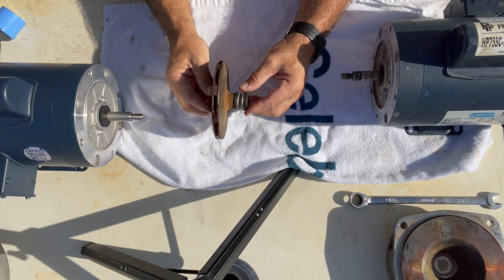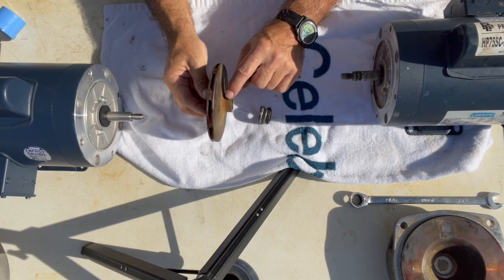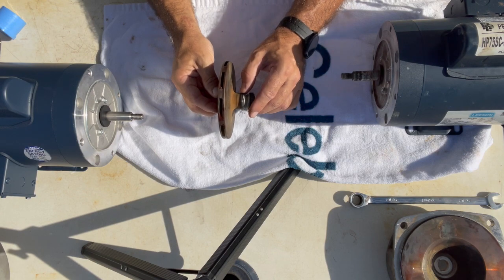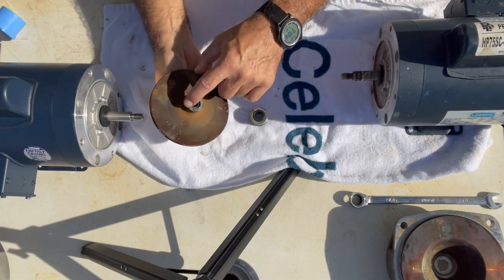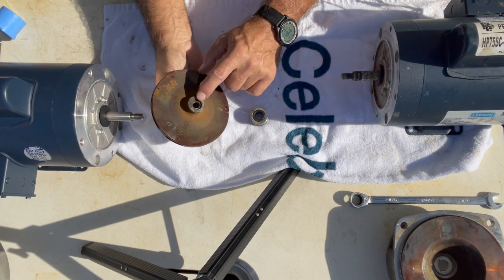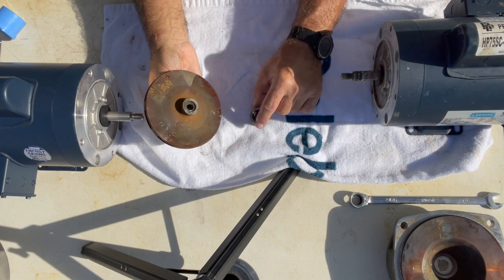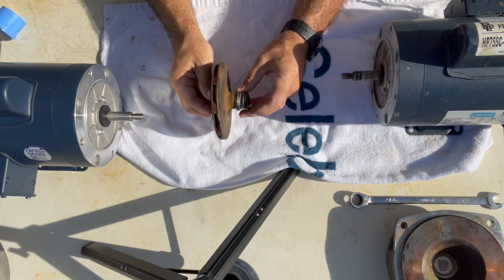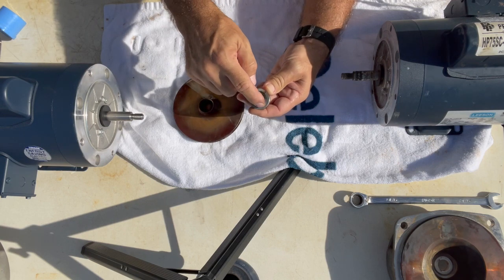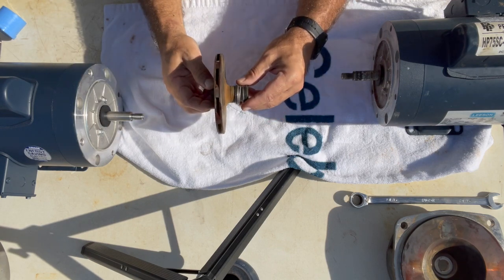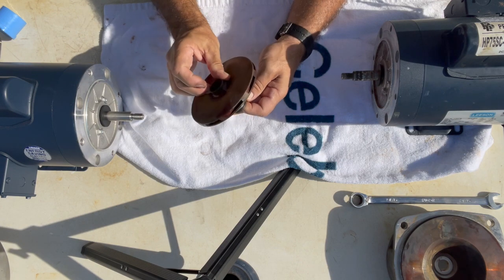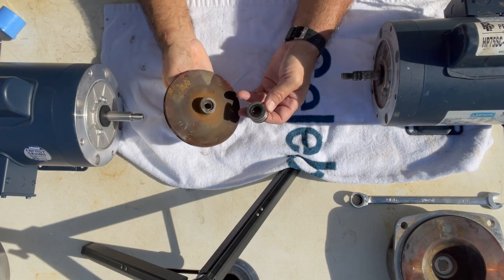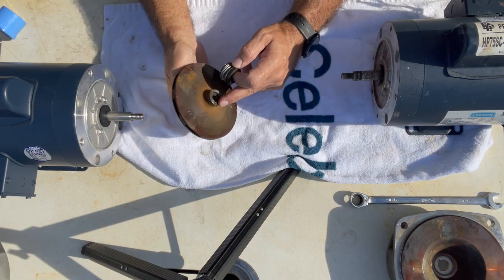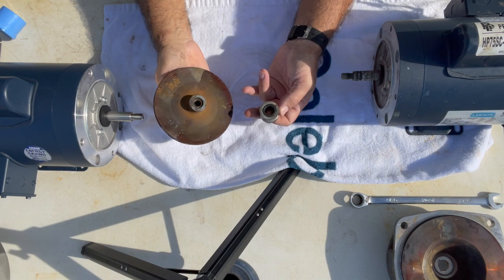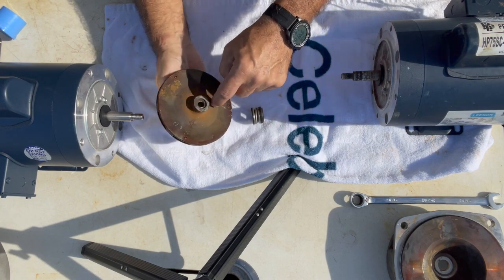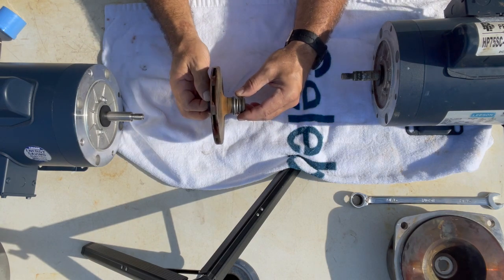The thing that frustrates me about this is, had they made this surface a little larger diameter so it was equal to the size of the seal, they could have put an O-ring in the back of this impeller that would have sealed up against this metal surface. Not only would water not get down the shaft because it has this double rubber seal, but that O-ring would help seal so no water got to the shaft at all. That would be such a better design, and I don't understand why engineers designing this kind of stuff don't do these simple steps, make the molding a little larger, put an O-ring in there, and you'd never have this problem.